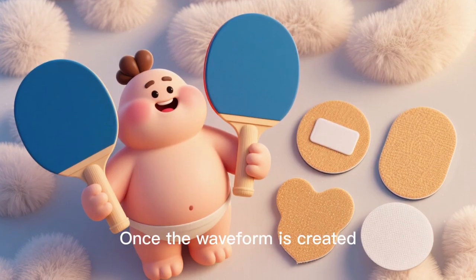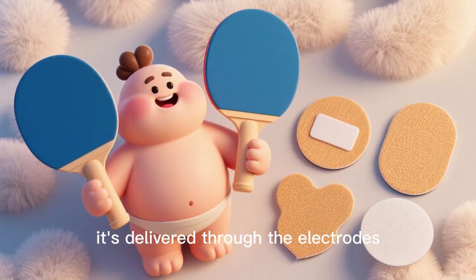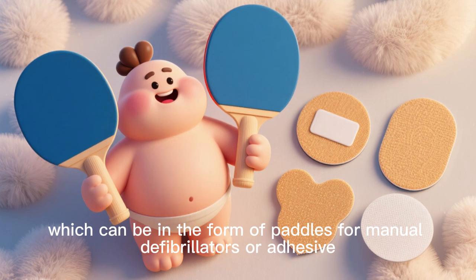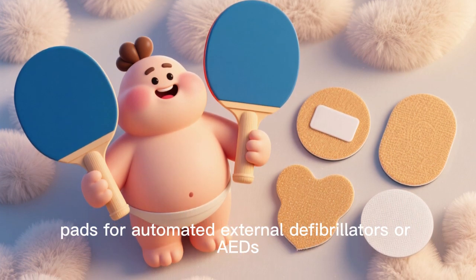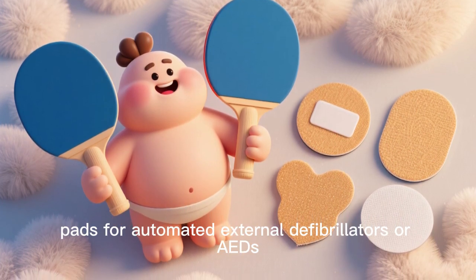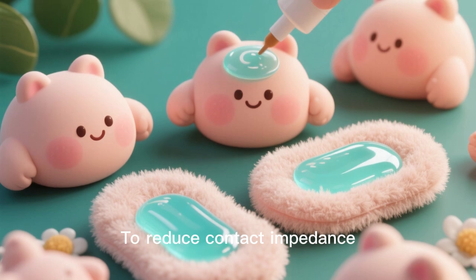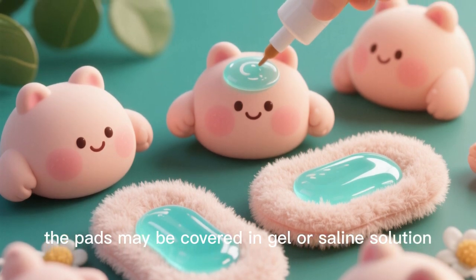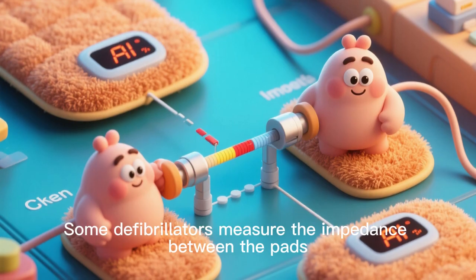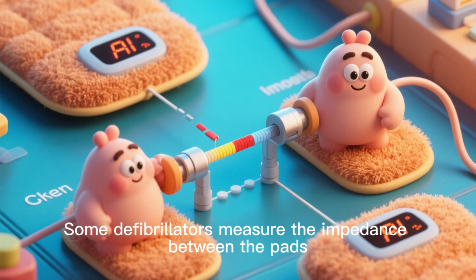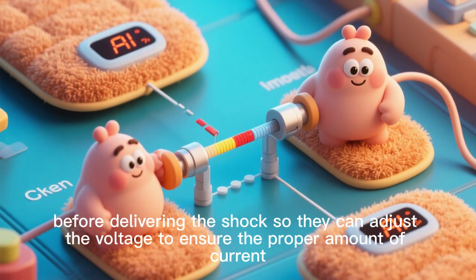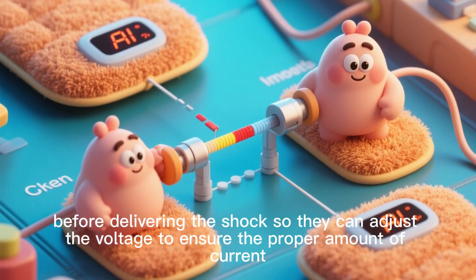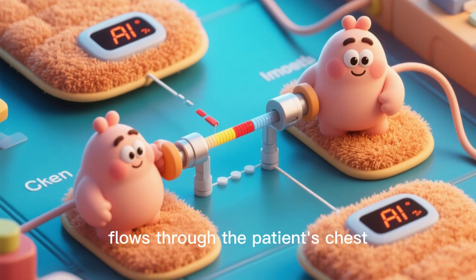Once the waveform is created, it's delivered through the electrodes, which can be in the form of paddles for manual defibrillators or adhesive pads for automated external defibrillators, or AEDs. To reduce contact impedance, the pads may be covered in gel or saline solution. Some defibrillators measure the impedance between the pads before delivering the shock, so they can adjust the voltage to ensure the proper amount of current flows through the patient's chest.